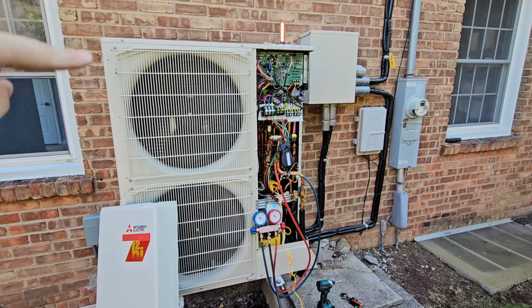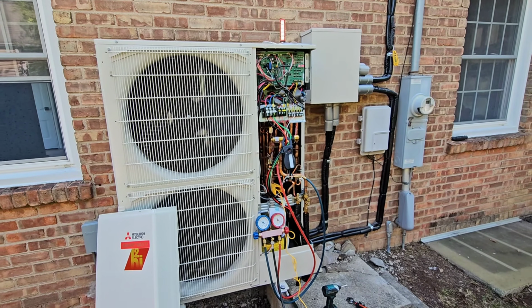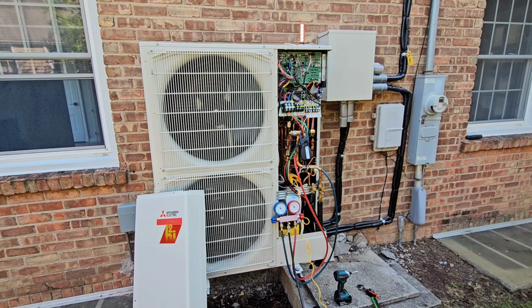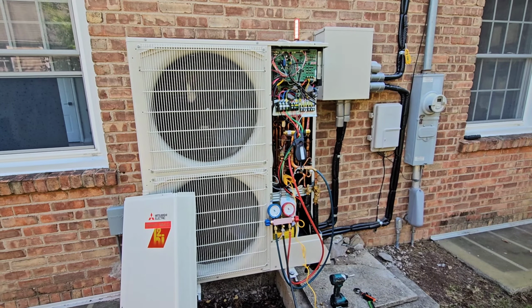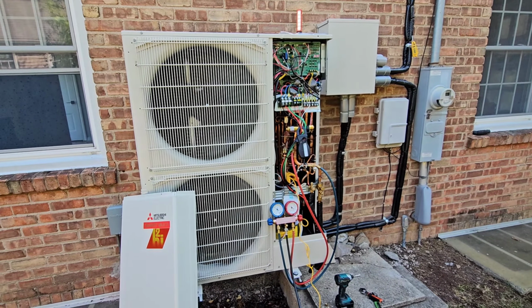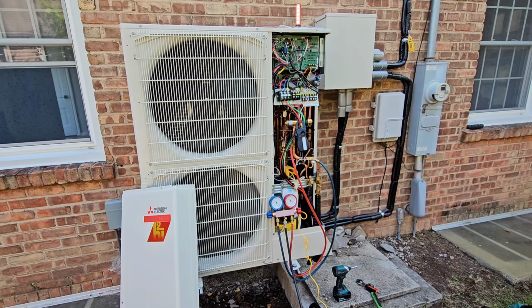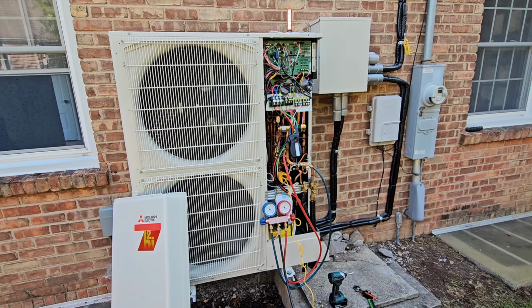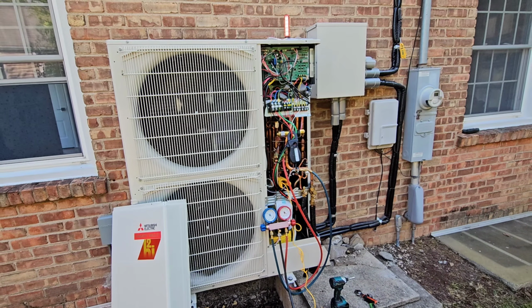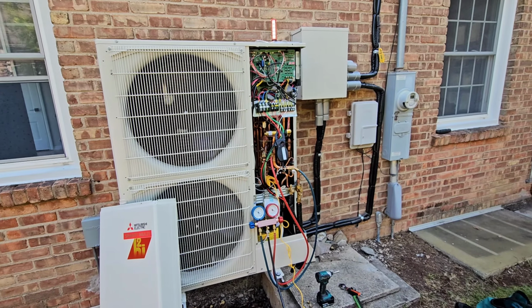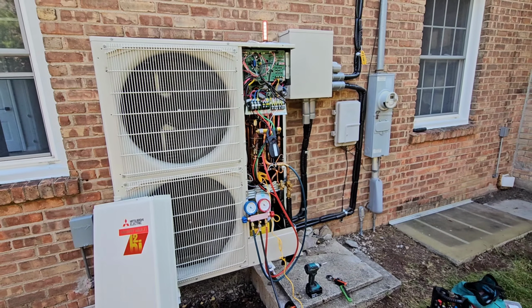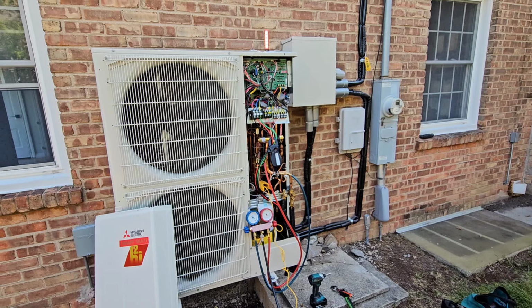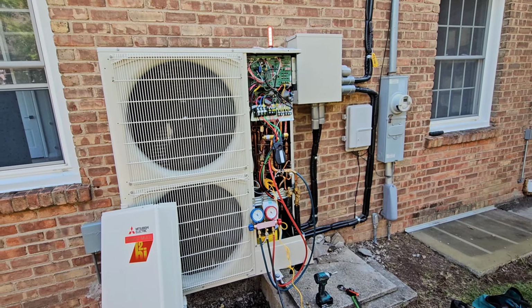So the one unit is what is called an inverter variable capacity heat pump. What that really means is, as the name says, variable capacity. It can adjust its heating or cooling output. Because it's a heat pump, it can heat anywhere from 20% to 100% in 1% increments. So it can adjust the speed, how much heating and cooling it's producing and injecting into the home, based on the outdoor temperature and how much is needed.